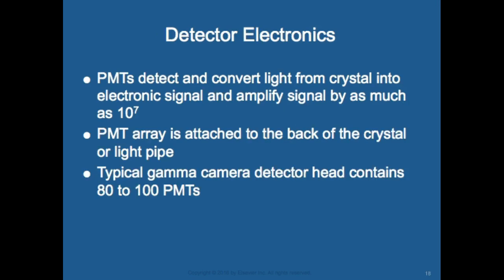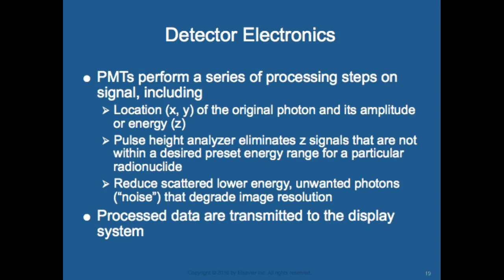The photomultiplier tubes (PMTs) detect and convert light from crystals to an electronic signal and amplify the signal by as much as 10 to the seventh. PMT arrays are attached to the back of the crystals or light pipe, and a typical gamma camera detector head contains 80 to 100 PMTs. PMTs determine the location (X and Y) of the original photon and its amplitude or energy (the Z pulse). A pulse height analyzer eliminates Z signals not within the desired preset energy range for a particular radionuclide.